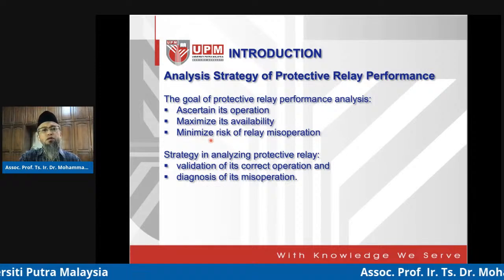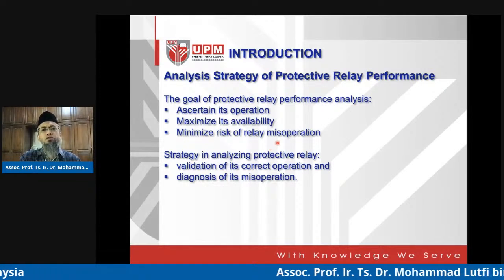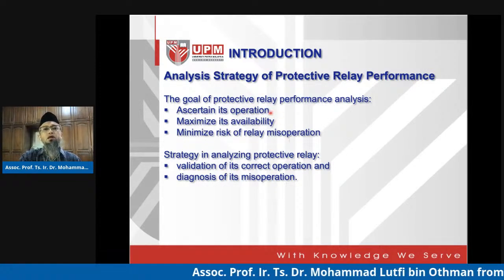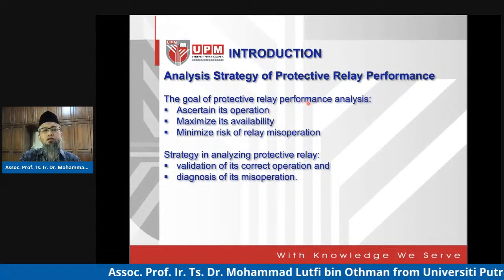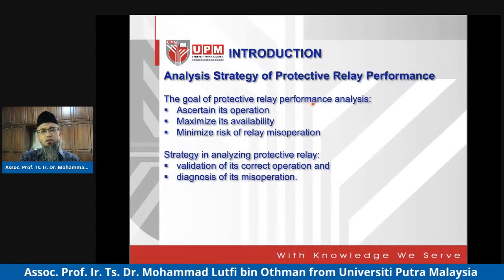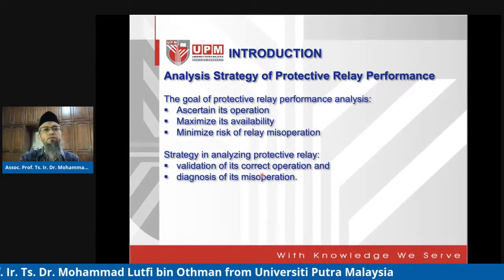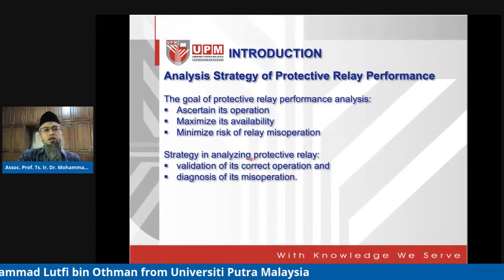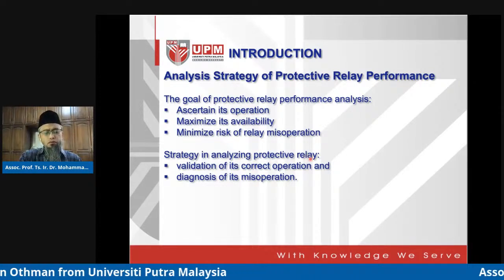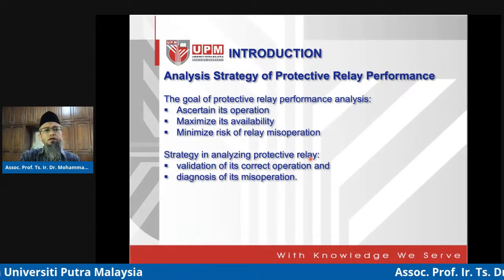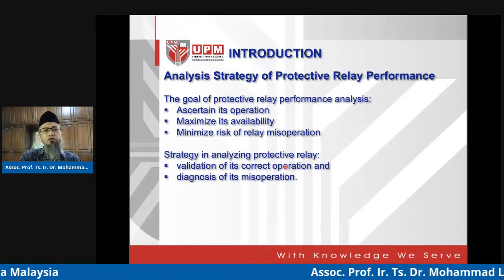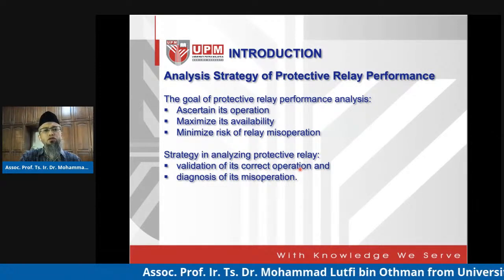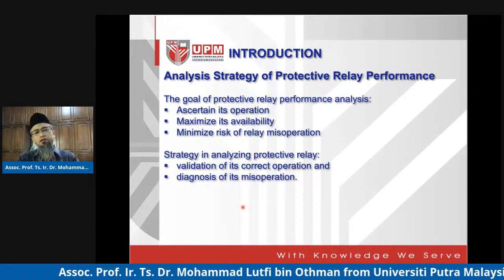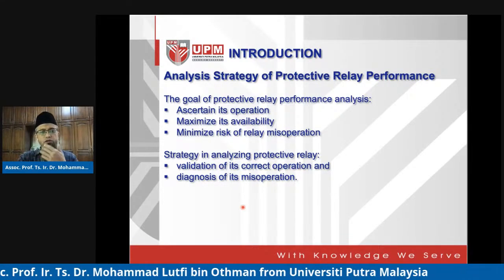And of course, we need to minimize the risk of relay misoperation. This is the goal of performance analysis, analyzing the performance of the protection relay. So the strategy in analyzing a protective relay is by way of validating its correct operation and thereafter diagnosing its misoperation. First, we validate if there's correct operation.